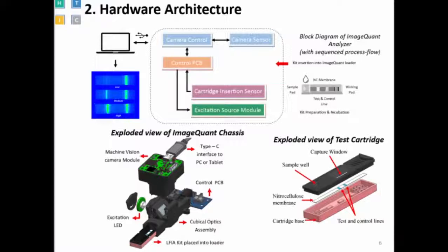I will give a brief about fluorescence measurement in the next few slides. The exploded view of the ImageQuant chassis includes the camera as the main sensing part and an excitation LED for the cartridge, shown in pink. The cartridge is a plastic piece containing nitrocellulose membranes inside, with test and control lines on that membrane. When a blood or serum sample mixed with reagents is dispensed, a biological reaction occurs, which is finally visible in terms of test and control lines.